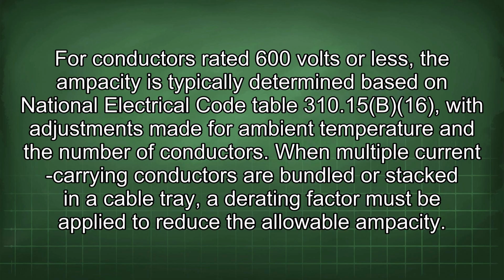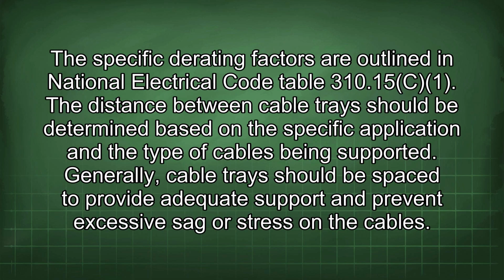When multiple current-carrying conductors are bundled or stacked in a cable tray, a derating factor must be applied to reduce the allowable ampacity. The specific derating factors are outlined in National Electrical Code Table 310.15(C)(1). The distance between cable trays should be determined based on the specific application and the type of cables being supported. Generally, cable trays should be spaced to provide adequate support and prevent excessive sag or stress on the cables.